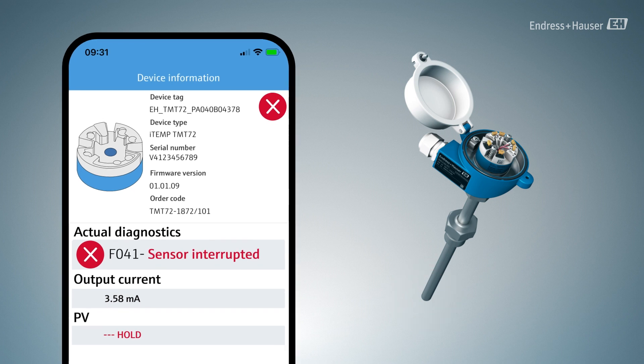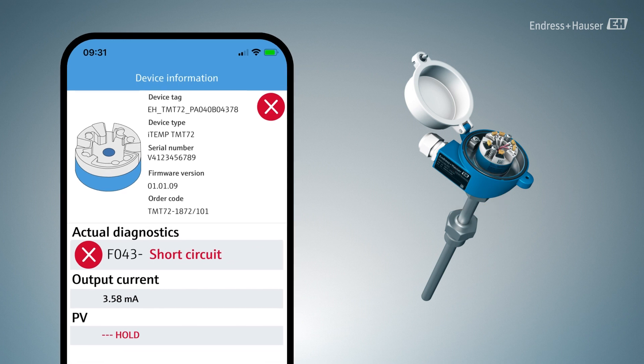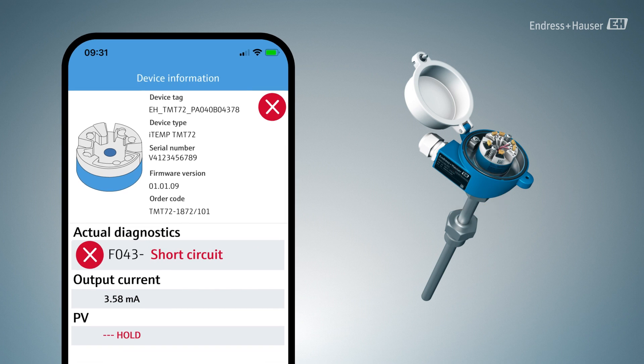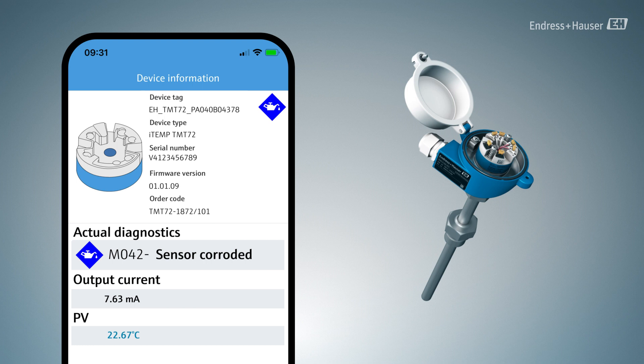Temperature transmitters offer the possibility to detect a wide range of errors in the sensor, transmitter electronics, process or environment, and help the user to ensure safe system operation. Diagnostic events such as sensor breakage and short circuit are standard in the device. For applications in harsh environments, additional diagnostics such as corrosion detection of the sensor cables provide even more added value. Information on possible corrosion can indicate future measurement errors and enables predictive maintenance.